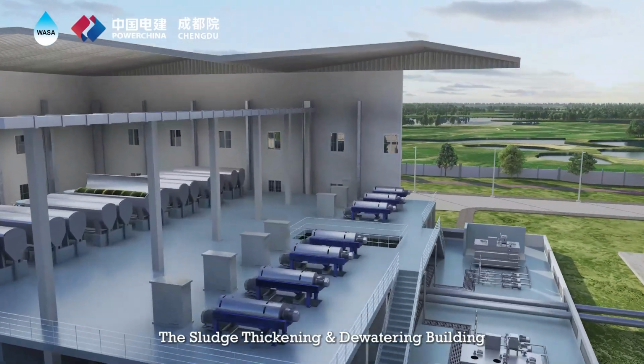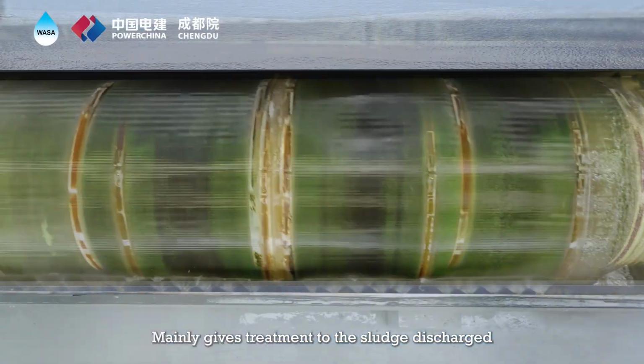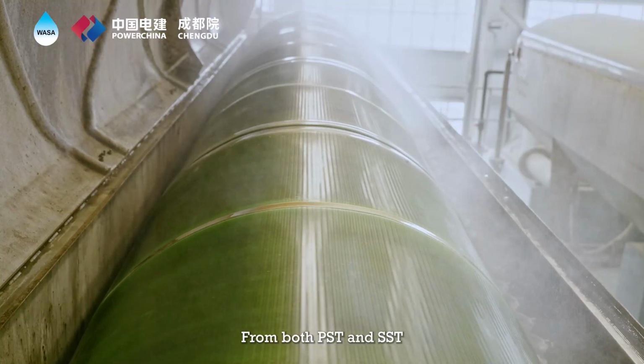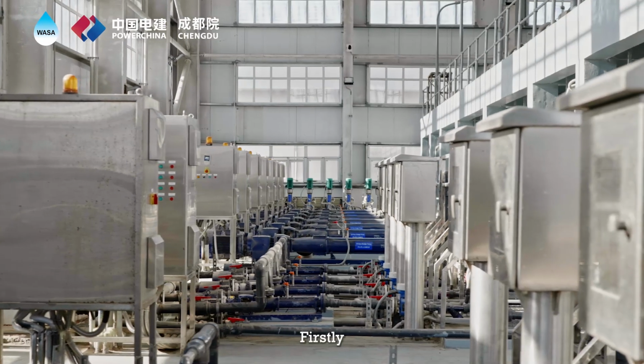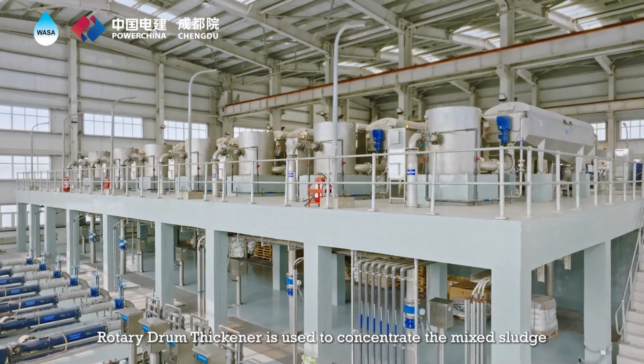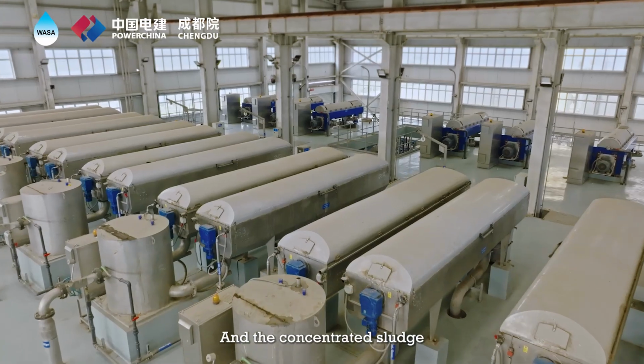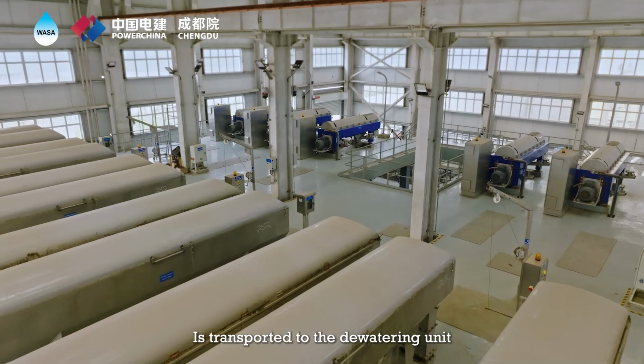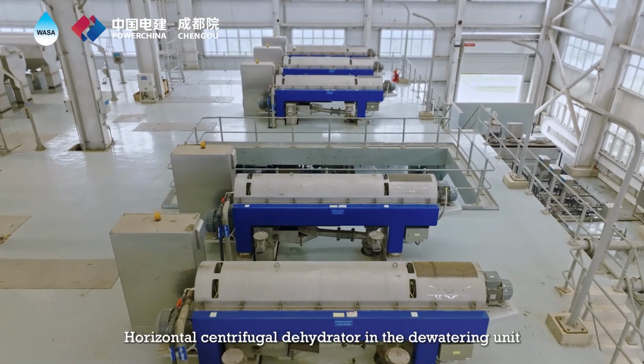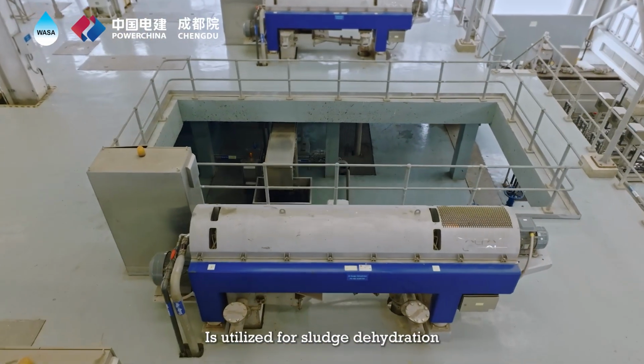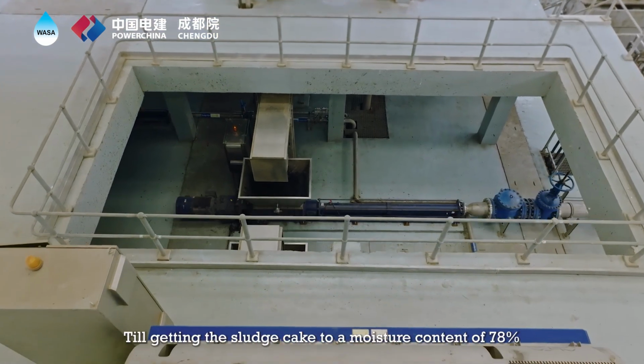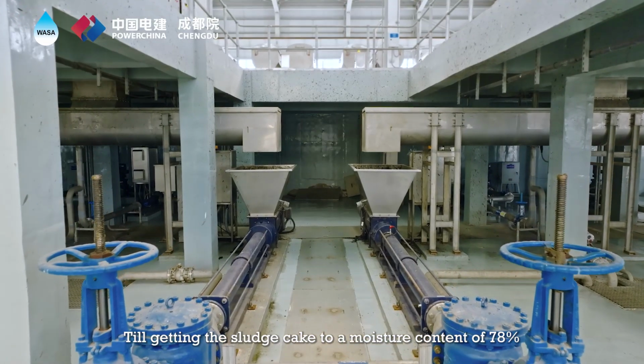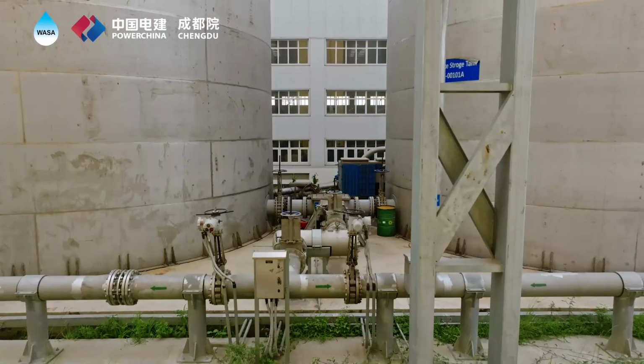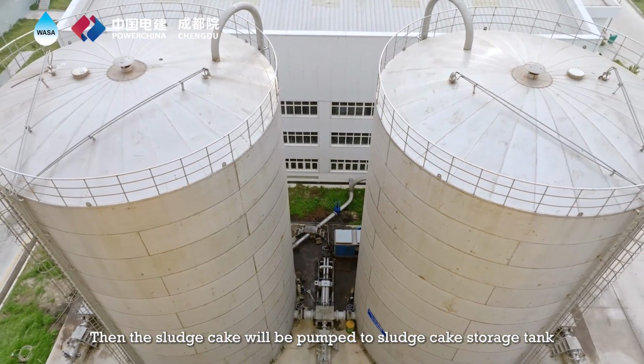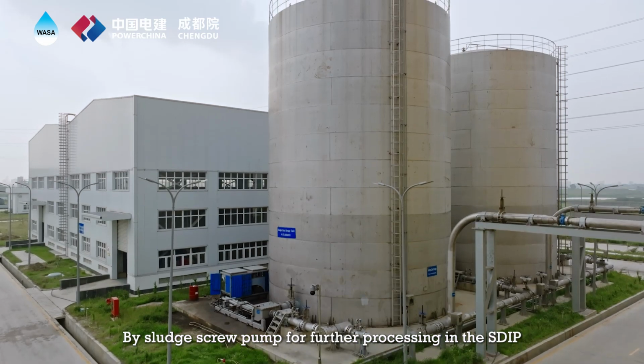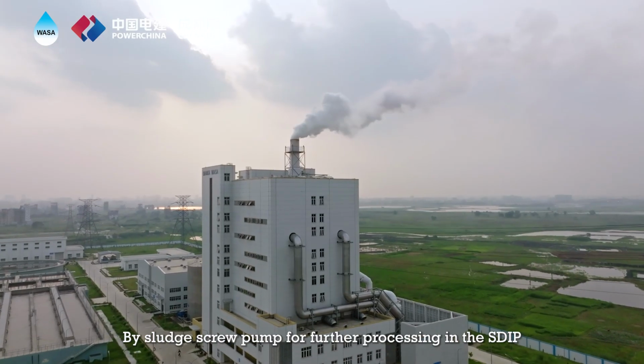The sludge thickening and dewatering building mainly gives treatment to the sludge discharged from both PST and SST. Firstly, a rotary drum thickener is used to concentrate the mixed sludge, and the concentrated sludge is transported to the dewatering unit. A horizontal centrifugal dehydrator in the dewatering unit is utilized for sludge dehydration until the sludge cake reaches a moisture content of 78%. Then the sludge cake will be pumped to the sludge cake storage tank by a sludge screw pump for further processing in the SDIP.